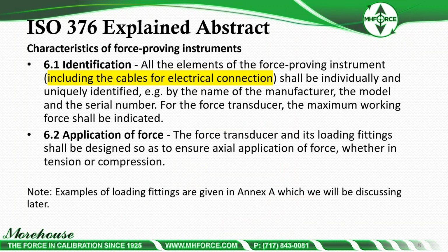Under 6.1 identification, all elements of the force proving instrument, including the cables for electrical connection, shall be individually and uniquely identified, e.g. by the name of the manufacturer, the model, and serial number. For the force transducer, the maximum working force shall be indicated. If you're an auditor, this is probably the number one deficiency on this standard if you wanted to write people up. I've yet to see people have a lot of their cables labeled and serial numbered. It is very, very rare working in our lab that we see a full system come in with serial numbers on the cables.